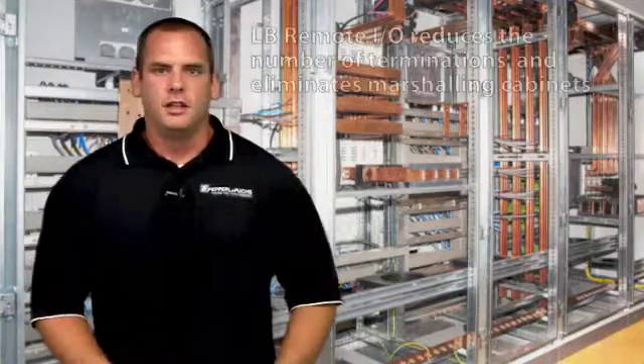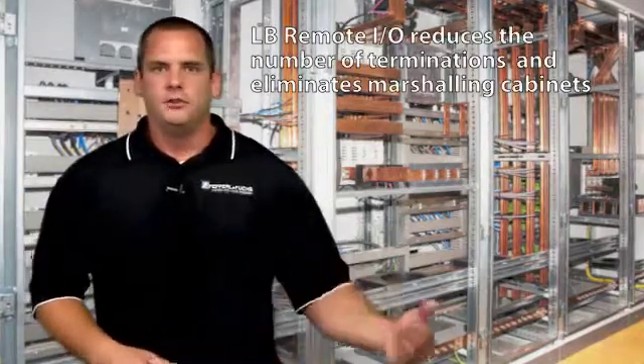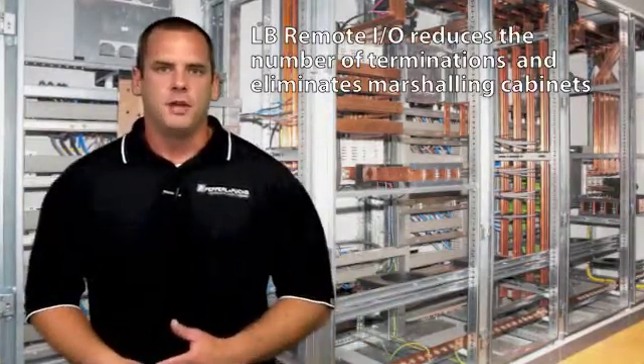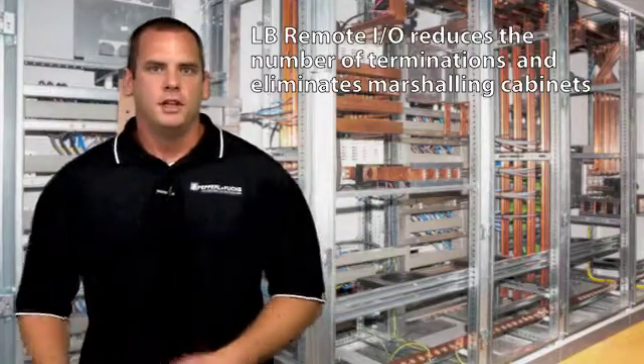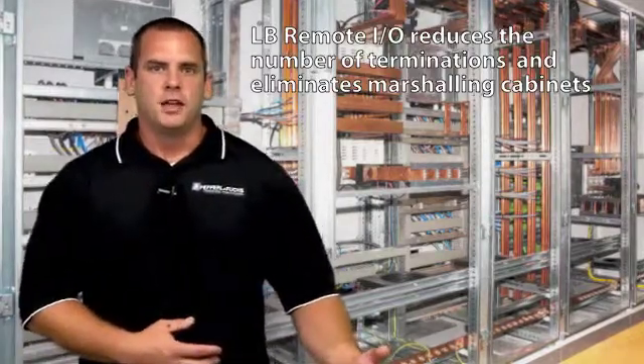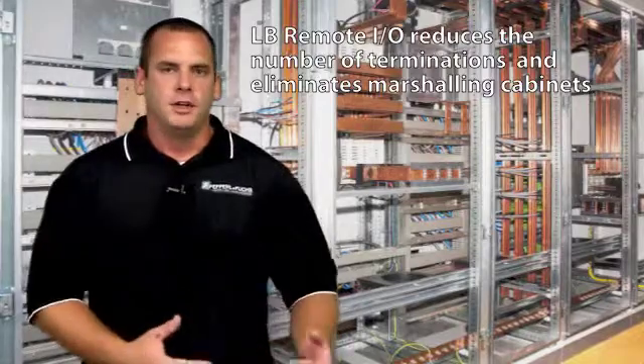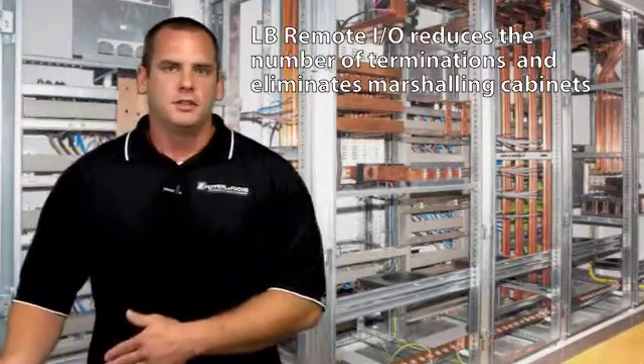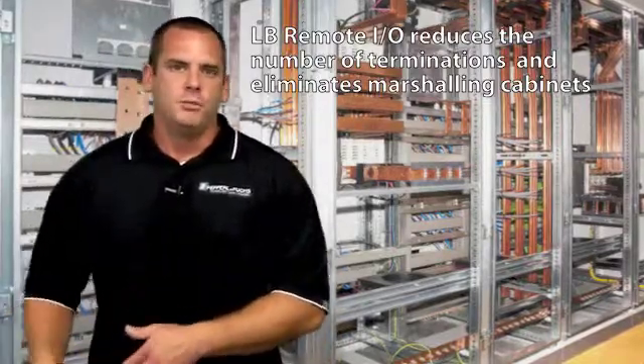Another great benefit is we're going to save you a lot of money on terminations and marshalling panels. Instead of having all of those point to point connections all the way back from the field to the control room, now they go to a local junction box with the LB and you make one termination to a single bus cable and that one bus cable goes back to the control room. One connection versus many is going to save you a lot of time and a lot of labor which all equals up to saving a lot of money.